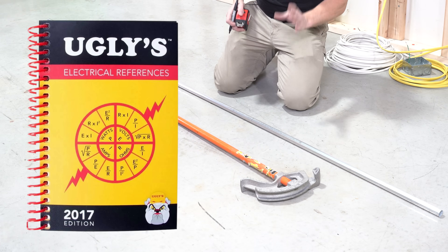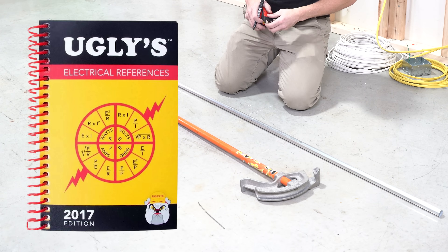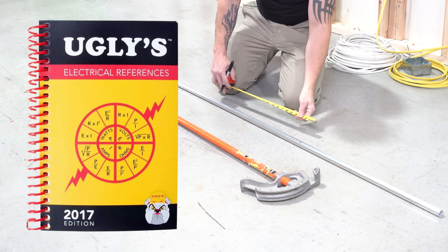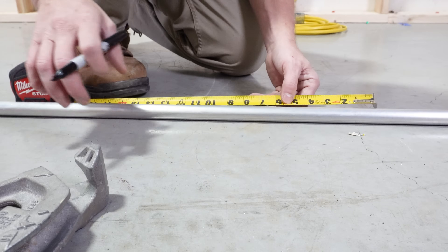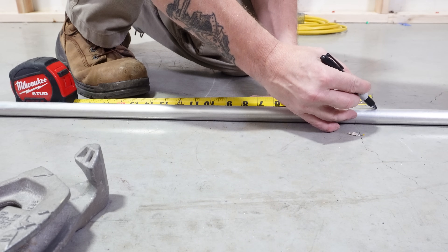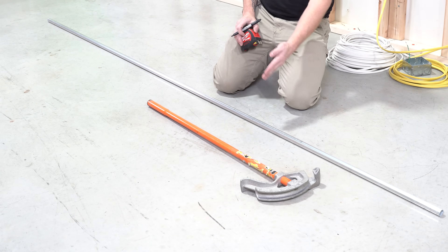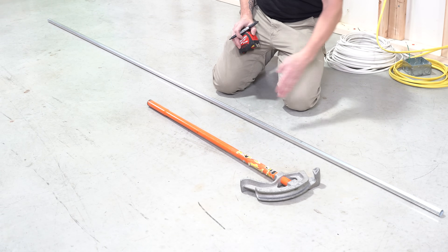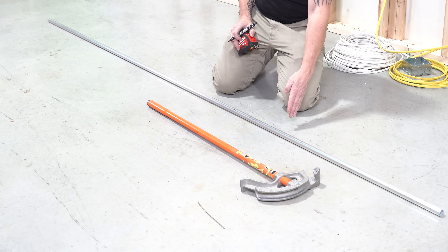This is all stuff that's in the Ugly's book, so keep one around. I just know it because I've been doing it for so many years. What I do is take six inches from my mark and go back and draw another line. That shows me two things: it shows me the end of where the 90 should be once it's a 36-inch bend, and it shows me where to actually bend it to achieve that.